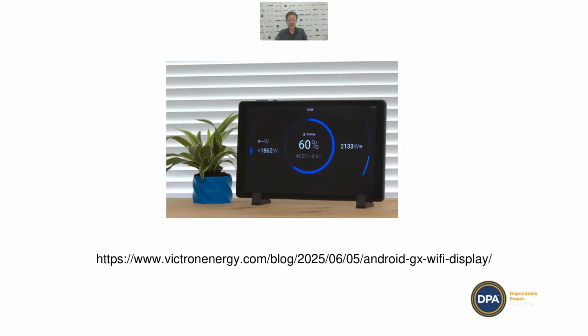In a previous webinar I did a section on setting up a remote GX screen, but what I wanted to show you now - let me stop sharing my screen and go to the camera - is this box I've created. Discover are bringing out a combiner box which will have Amphenol plugs on the bottom and 5 125 amp breakers in it. That will allow you to put 3 Helios batteries into it and then use the other 2 to go to either a larger inverter, or use a single pair to go to a smaller inverter. It's going to be Amphenol to Amphenol from the batteries into this combiner box, and it's going to be a really quick and easy installation.